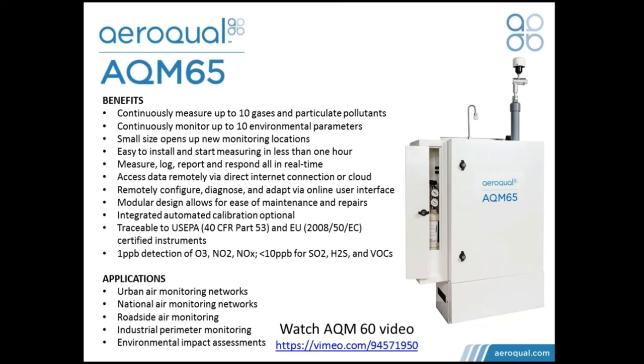It's a modular instrument, which aids maintenance and repairs. It can be fabricated for one application and then changed for another. One key difference with this product is that the calibration of the gas modules is according to US EPA 40 CFR Part 53, which also equates to the EU method under 2008/50/EC. So the measurement or calibration is traceable to certified instruments. We're not talking PPM level of detection - we're talking PPB levels for ozone, NO2, NOx, and below 10 PPB for SO2, H2S, and VOCs, etc.